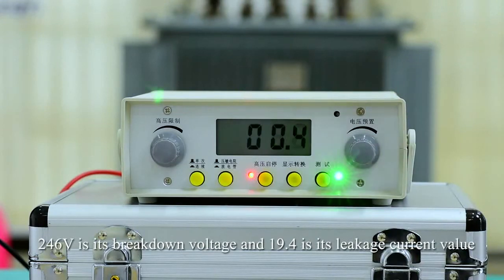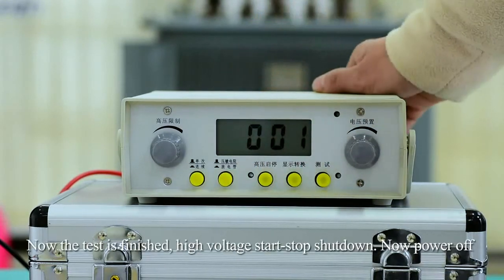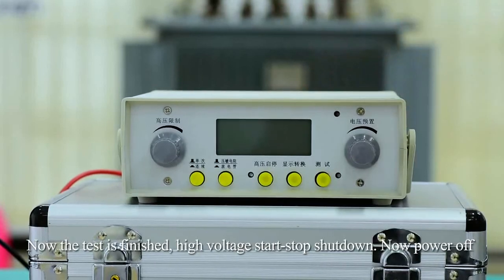246 volts is the breakdown voltage and 19.4 is the leakage current value. Now the test is finished. High voltage start, stop, shut down. Now power off.